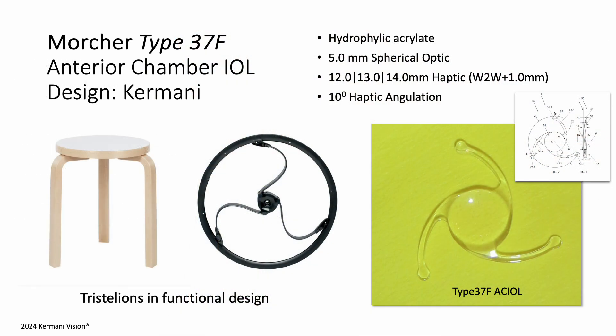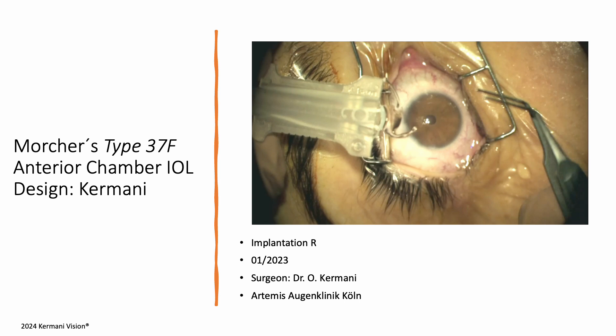Olaf Morcher, CEO of Morcher Company in Germany — a company with 70 years of eye surgery expertise — approved the proposal that I made. The new anterior chamber lens is made of proven hydrophilic acrylate, measures 12–14 mm in overall diameter based on the patient's white-to-white measurement, and features a 5 mm spherical optic. It has three haptics arranged symmetrically in a tristelion angle to ensure smooth aqueous humor flow without requiring iridectomy. This is the Morcher Type 37F anterior chamber lens.